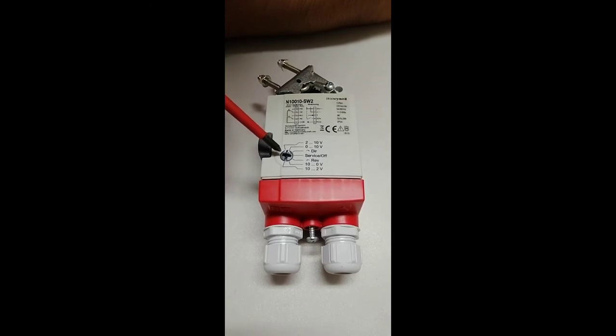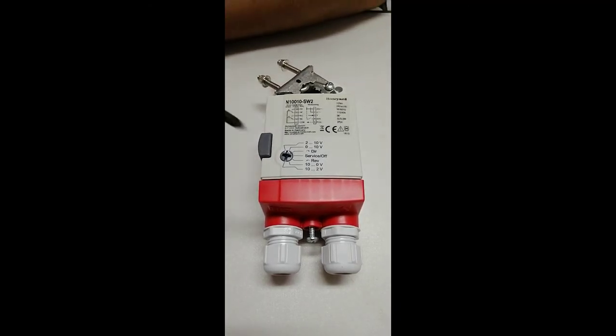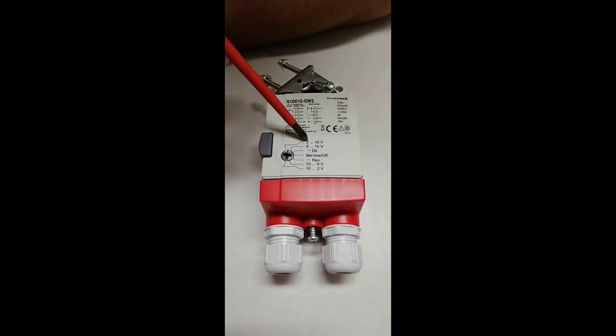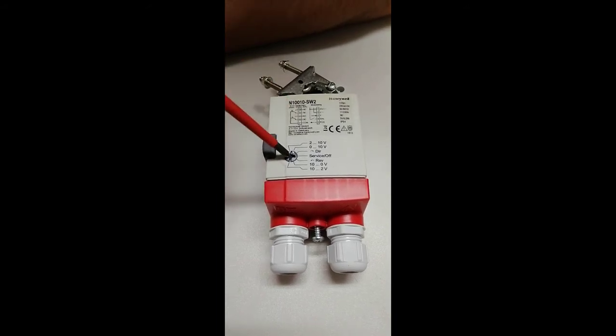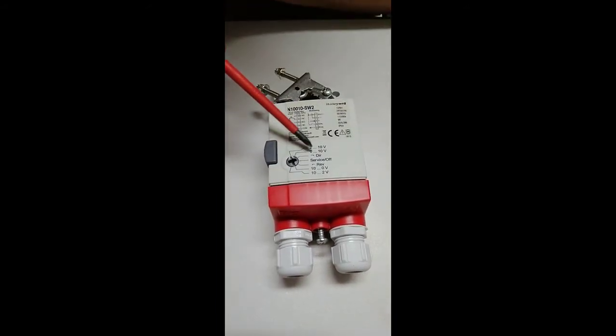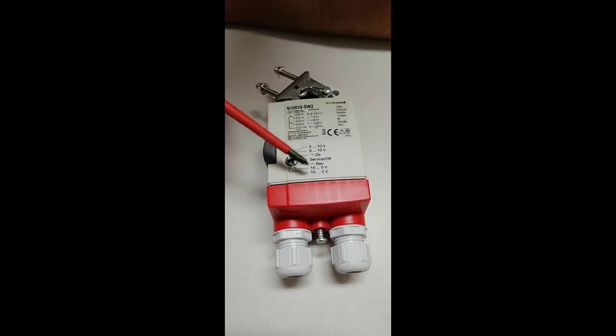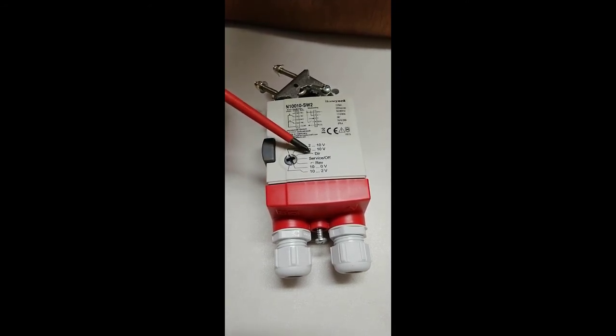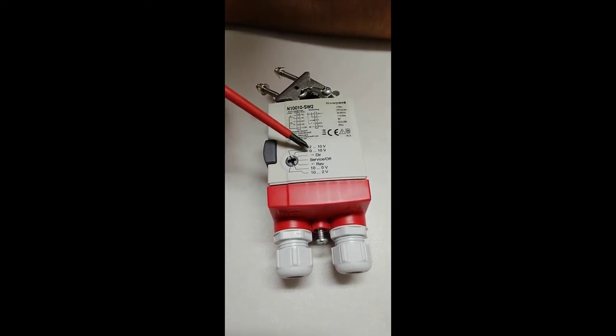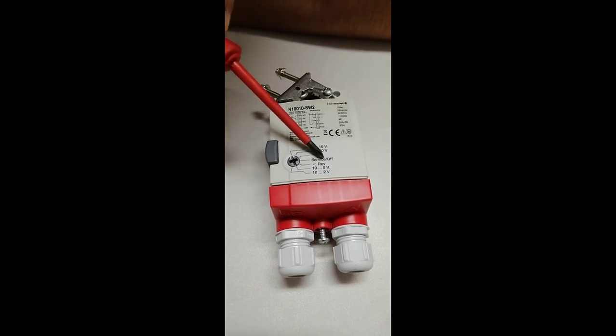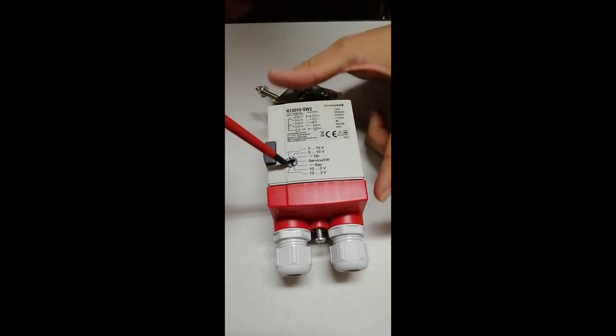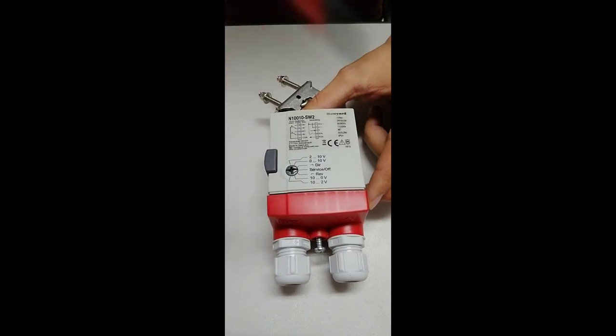Similarly, we have a knob here to select what type of control signal we have. If we have a 2 to 10 volt signal, we can select it like this. Then 0 to 10 volt signal, 10 to 0 volt signal. We can also select the direction, like direct acting or reverse acting. Or if we want to keep it off, we select the off position. Then here we have connections.